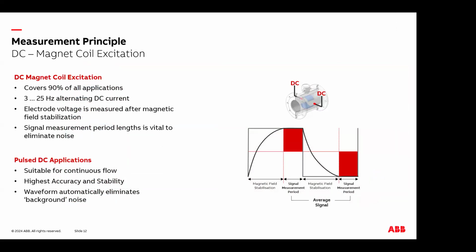Yep, thanks, Mo. As Mo explained, we have a magnetic field that is generated. This magnetic field is generated either by giving an AC current or a DC current. Depending on the application, the choice of the excitation is decided. In case of DC excitation, you choose it when you need good low flow stability and better accuracy. And when you choose an AC excitation, it depends on the process. In sluggish, slurry kind of process liquids, you would use the AC pulse excited flow meter versus a DC pulse excited flow meter. Thank you.